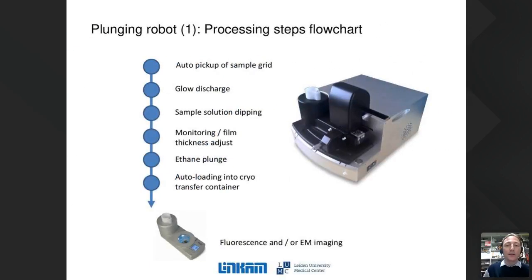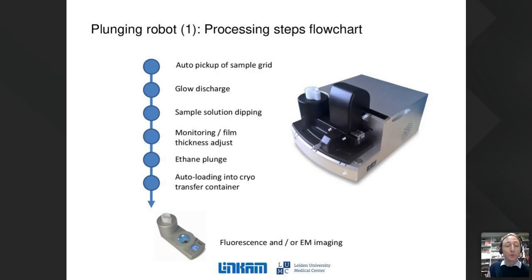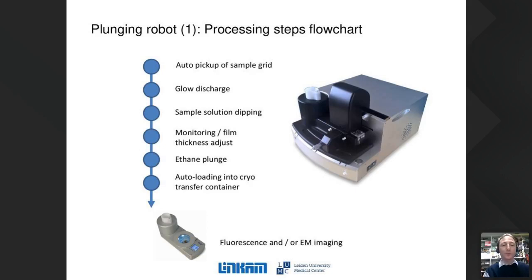We have designed and implemented a device where many of these tasks are automated, using a fundamentally different process to adjust the film thickness before plunging. The steps are: automatic pickup of the sample grid, glow discharge to make it hydrophilic, applying sample by dipping into a sample solution or pipetting, monitoring the sample with a real-time built-in optical microscope, adjusting the film thickness, plunging in liquid ethane, and automatically loading into a cryo transfer cartridge for processing.